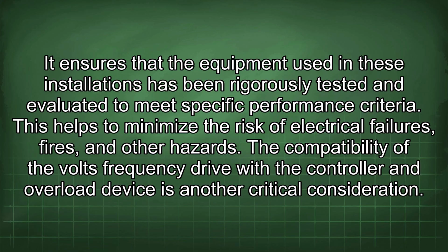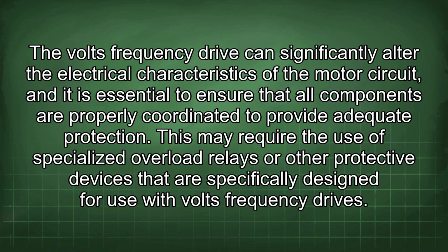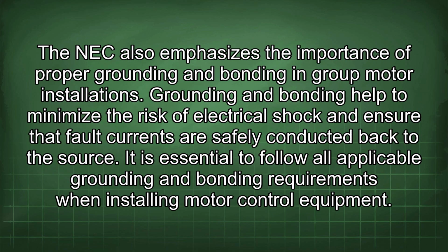The compatibility of the volt-frequency drive with a controller and overload device is another critical consideration. The volt-frequency drive can significantly alter the electrical characteristics of the motor circuit, and it is essential to ensure that all components are properly coordinated to provide adequate protection. This may require the use of specialized overload relays or other protective devices that are specifically designed for use with volt-frequency drives. The NEC also emphasizes the importance of proper grounding and bonding in group motor installations.